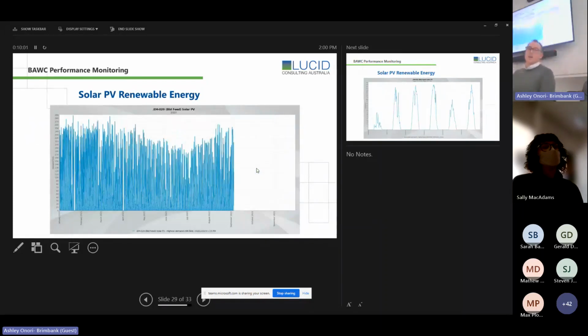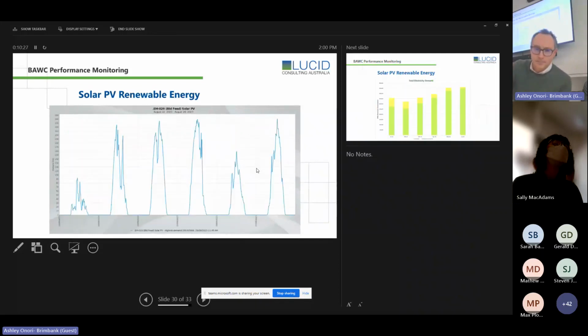This is the actual PV output from this facility, from the 500 kilowatt system. There's an issue we're resolving with the accuracy - we think the meters need calibration, because it shouldn't be maxing out. A 500 kilowatt peak system shouldn't max out at 290 kilowatt real power. It definitely won't max out at 500 - there'll be losses, but it should be much higher than 290. So that's another issue we're working through.